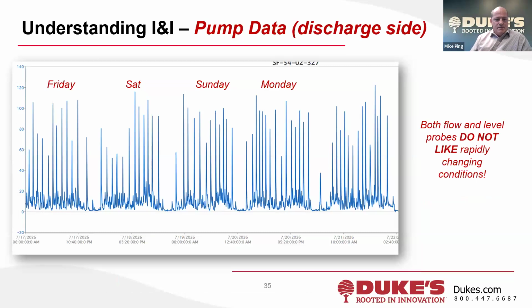This is very current data. You can see each day there's a pause in the middle of the night where the pumps are mostly not on, with very low flow rates. In fact, those flow rates could be so low that the velocity is too low to get a good measurement, or the level is too low, or both. Open channel equipment likes good velocity and good level to get good quality data.